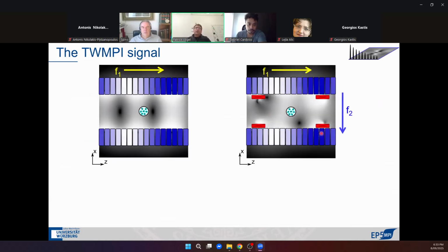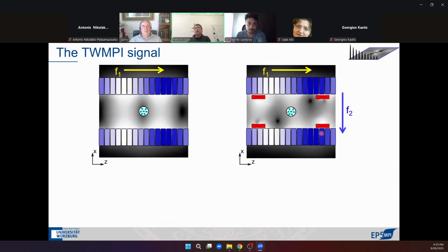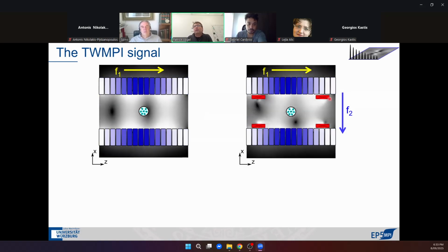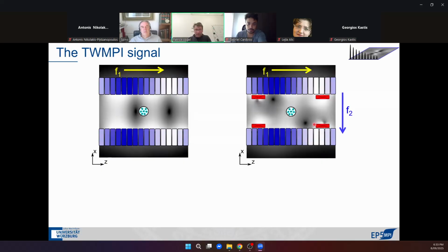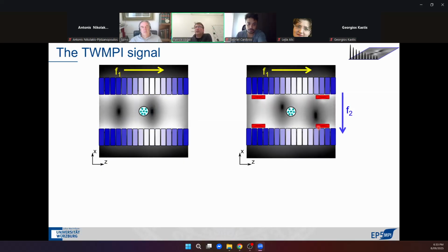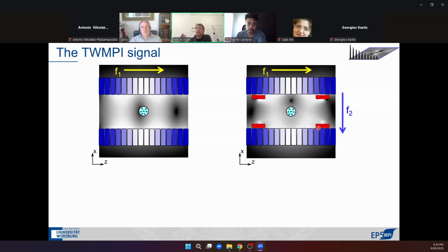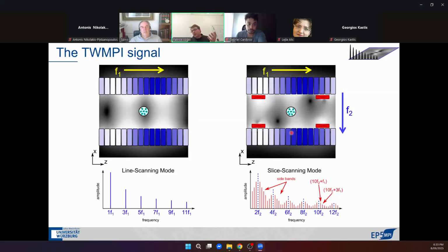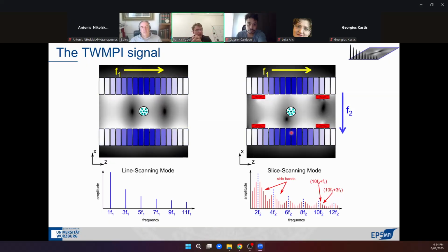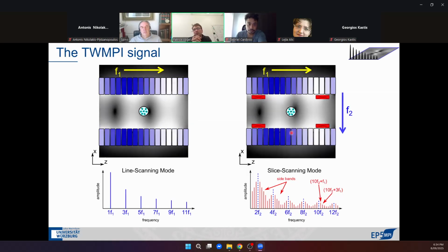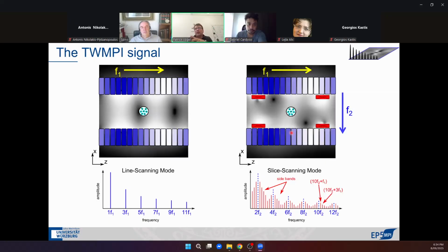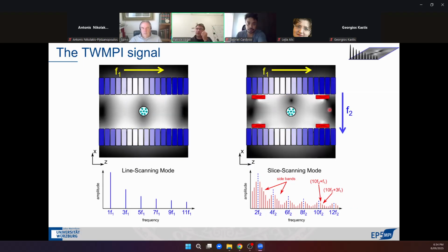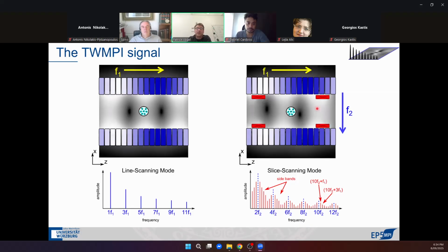When you are now doing, for example, a 2D scan, you are using a second frequency. So you have the first one, the traveling frequency from left to right, and then for encoding a slice, you need a second frequency, which here goes from up to down. And from the second frequency you also get higher harmonics of the particle system as the magnetization response. Together, you get a whole bunch of higher harmonics in the spectrum of a signal created within such a scanning mode.